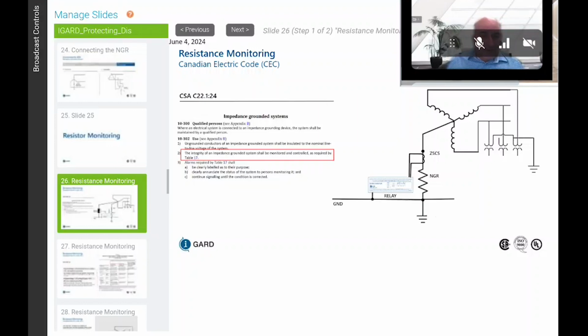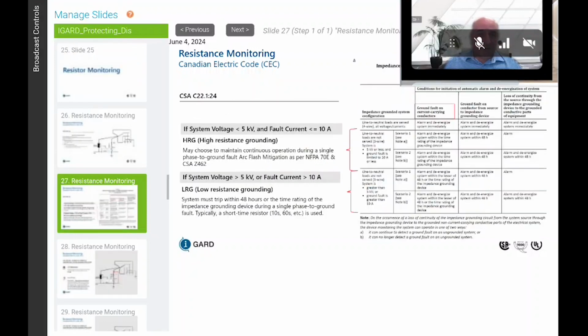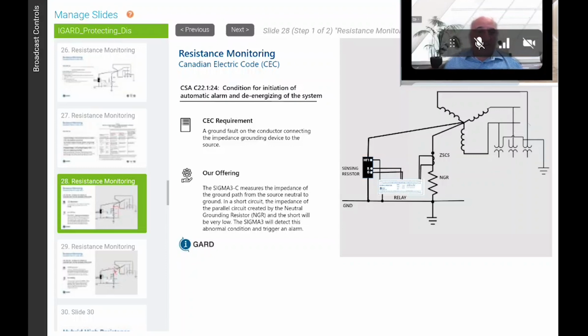The integrity of the impedance grounded device shall be monitored, as required by 14, table 17. So table 17 basically says, if you have a high resistance grounded system or low resistance grounded systems, you must do one of these things. And the only thing that really changes is a loss of continuity. So if your resistor becomes open circuited, you have to do something, either alarm or alarm within 48 hours. And the difference between these two clauses is whether you have the ability to detect a ground fault on an ungrounded system or not. And you'll get the slide so you can see this.